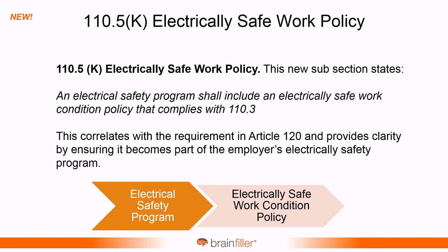Another new addition, the electrically safe work policy. It's a new subsection, and it just states that an electrical safety program shall include an electrically safe work condition policy that complies with 110.3. Now, this may seem maybe obvious, but now it's part of NFPA 70E that if you develop an electrical safety program, it has to have in there the electrically safe work condition policy. So this is a requirement. Now, again, emphasizing electrically safe, the electrically safe work condition.